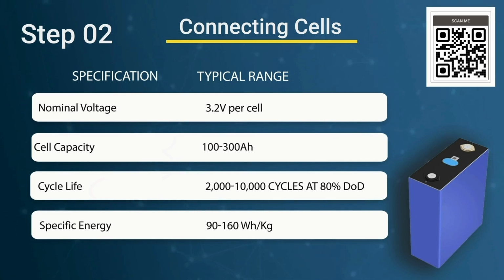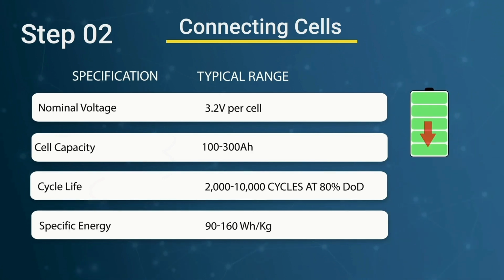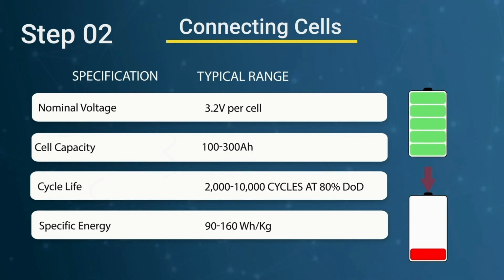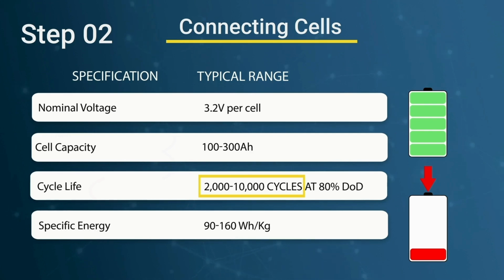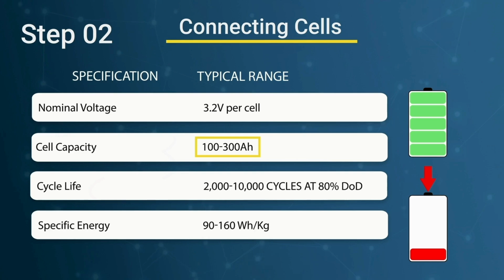The following table includes the main key features and specs that one should consider when selecting a LiFePO4 cell technically. Depth of discharge refers to the percentage of a battery's total capacity that has been used. For example, if a 100 ampere-hour battery has discharged 80 ampere-hours, it has an 80% DOD. A higher DOD allows you to use more of the battery's capacity, but it can also reduce the battery's lifespan. Cycle life is the number of complete charge and discharge cycles a battery can undergo before its capacity degrades to a certain level, typically 80% of its original capacity. The more cycles a battery can endure, the longer it will last. The cell capacity is the total amount of electrical charge a battery can store, measured in ampere-hours.